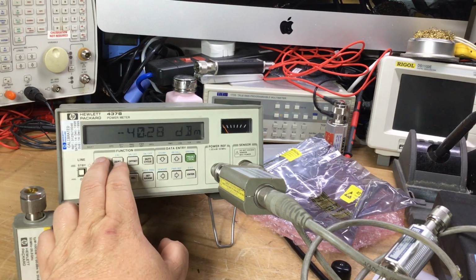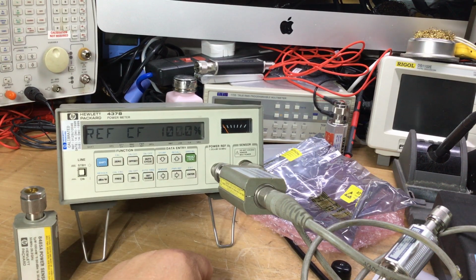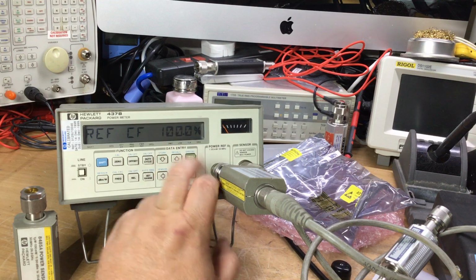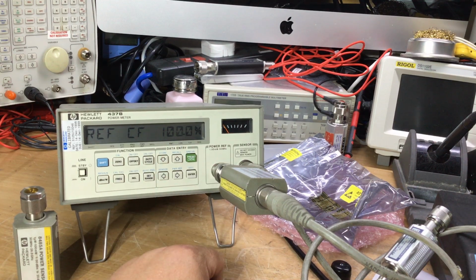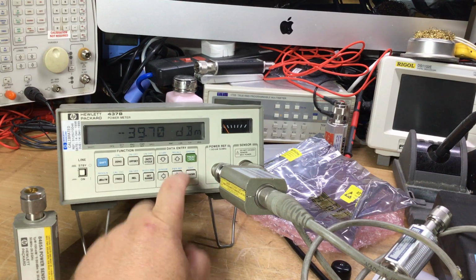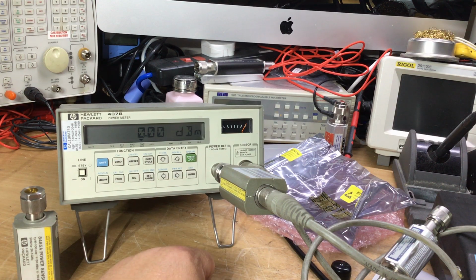So this time when we do a cal, it'll ask us for the cal factor, which is 100% as per what's on the sensor, and then we just hit enter, and now it's going to cal it. Now as part of that process, it'll range it obviously, and then it'll deliver the measurement there. Now if I do shift and reference again, then it should read 0 dBm, so that's correct.